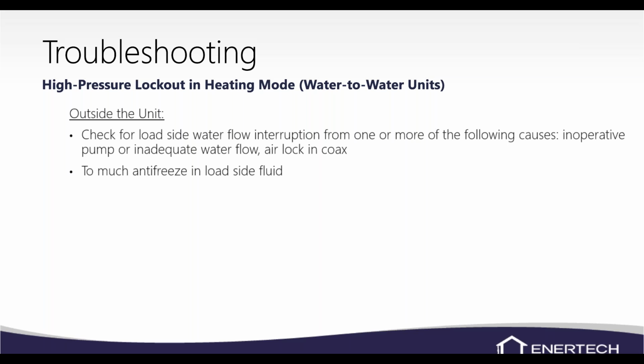Too much antifreeze, so we're not transferring good heat on the load side. If you're only doing heating, we don't necessarily have to have antifreeze on the load side, unless it's running through like a floor zone that's in the garage or something like that, then I would highly recommend it. But if you're doing any kind of chilled water with a water-to-water unit, then we definitely want antifreeze on the load side, and make sure we've got proper amount of antifreeze.